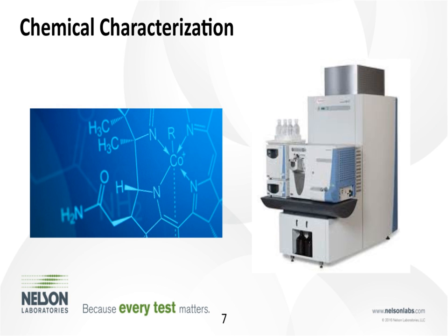Now moving on to chemical characterization. I chose to spend more time here because we're seeing this requested more frequently, and also the approach to establish a full extractable leachable profile is generally more involved and requires the use of multiple instruments, and it just requires more time to accurately talk about. The goal of using chemical characterization is to yield quantitative amounts of chemicals that could extract or leach from a device in order to determine the toxicological hazard to the end user of that device.